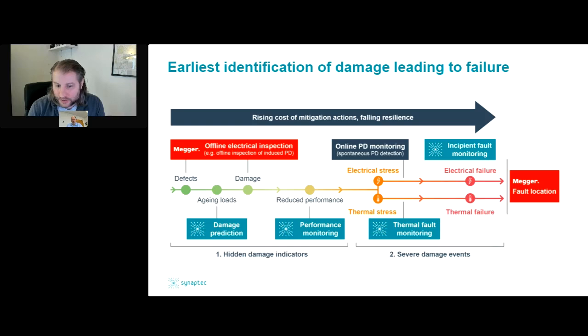There are two categories here. There are hidden damage indicators, things that are relatively subtle and difficult to find, but by monitoring every joint, looking at temperature or screen currents, we can build a picture of what's normal and generate alarms if something drifts outside that norm. Then there's the second category, more severe damage events, where it's becoming obvious there's a failure.